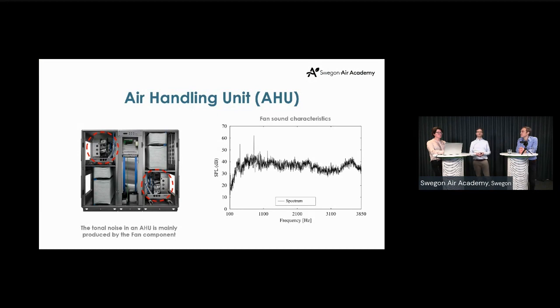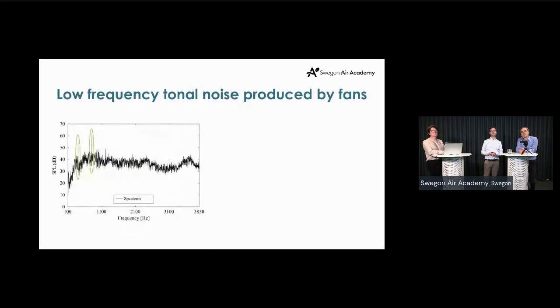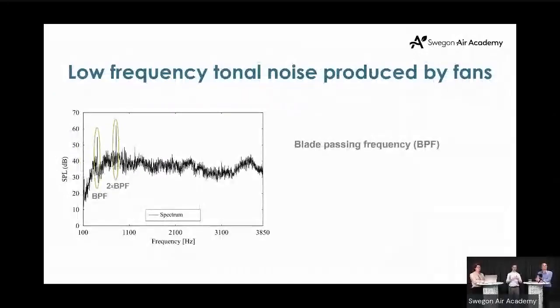If we take a look at the spectrum of one of these commonly used centrifugal fans, it looks something like this, where we have 2 tones here in green. What are these tones? They are the so-called blade pass frequency and its first harmonics. The blade pass frequency was coined before, when we have a casing or a volute around the fan.